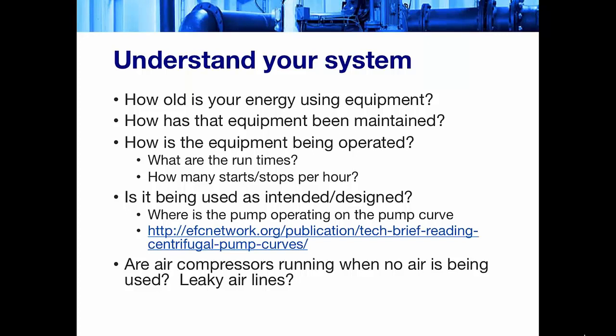And then another big one for consumption of energy is air compressors. So if you have a plant that has valves that are opened or closed with air, and you realize that your air compressors are running even when no air is being used, it's a good indication that you've got leaky air lines and you're wasting a lot of energy. So look for ways within your system to optimize your operations. Next slide, please.